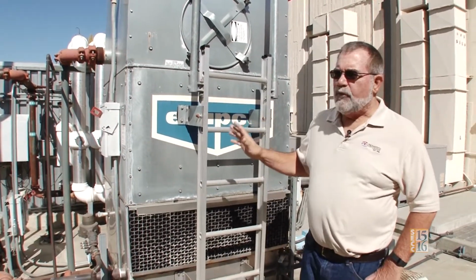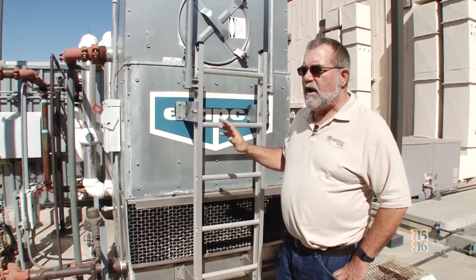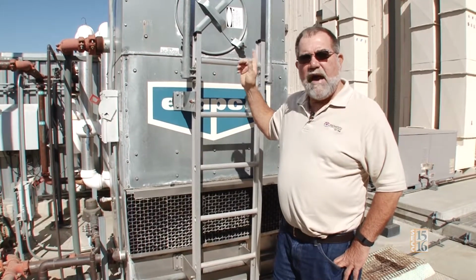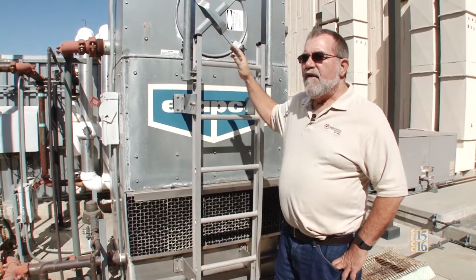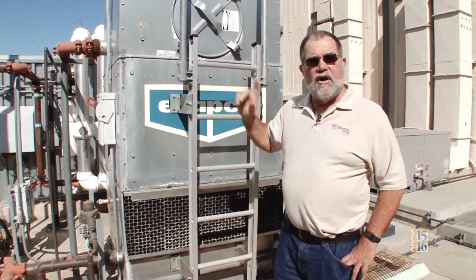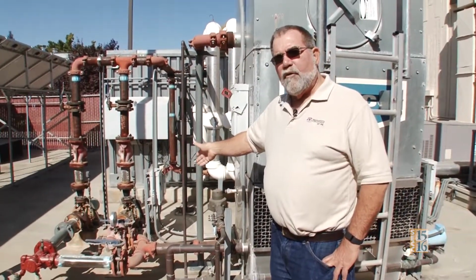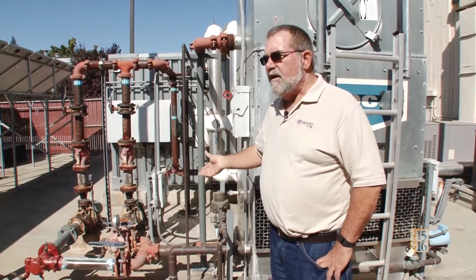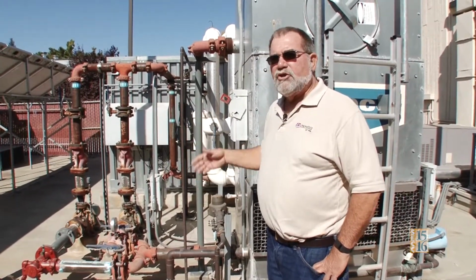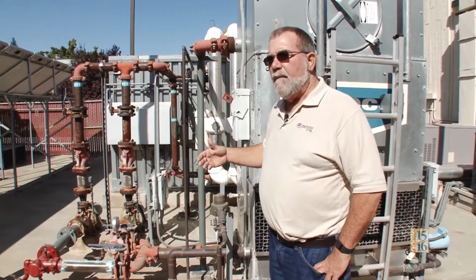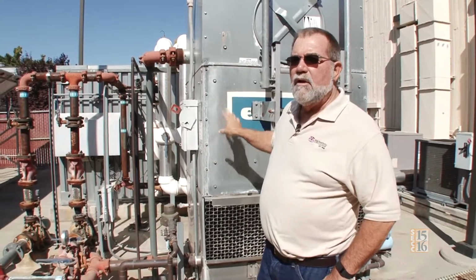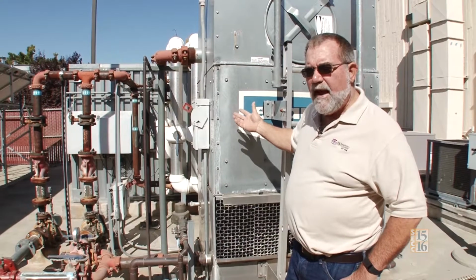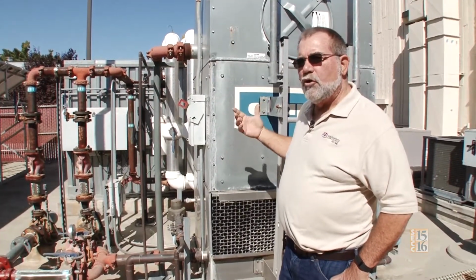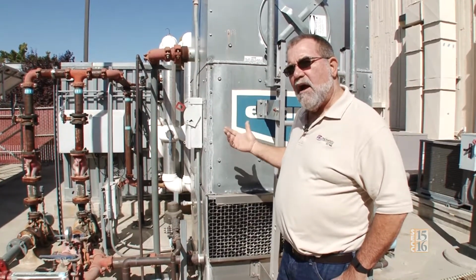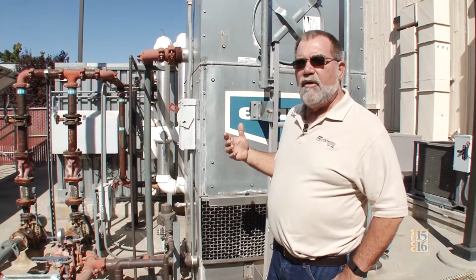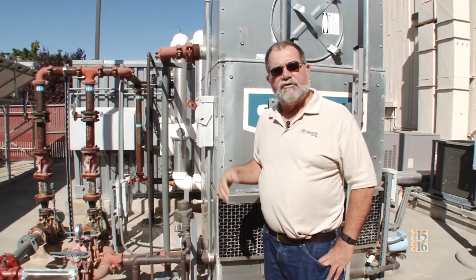One of the things I try to impress upon students when they walk past this cooling tower is to listen to the sound, to learn how a properly operating cooling tower should sound. If I didn't hear this noise at this level, that would tell me there's a problem, probably with one of our pumps — maybe it lost its prime, there's air in it, or a valve is closed, but something's wrong, and that leads to other issues from lack of proper water flow. This is another example of a living lab, where we're around the equipment and learn how it sounds, using our ears as a primary method of detecting whether equipment is operating correctly or malfunctioning.